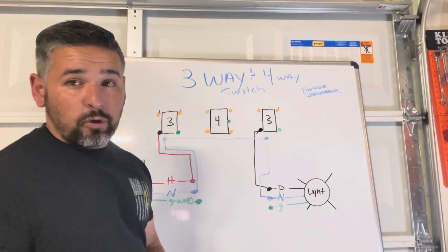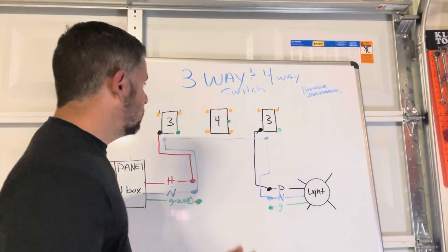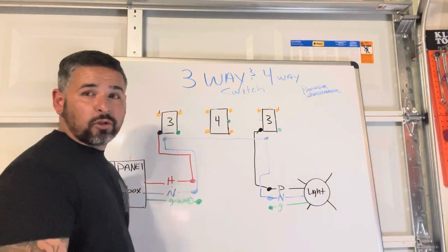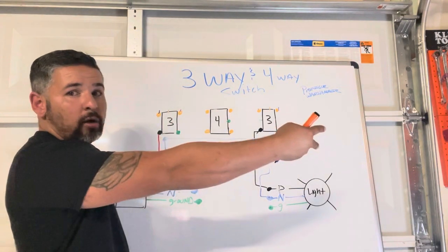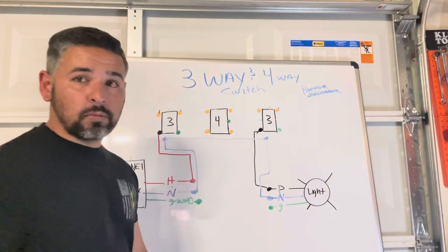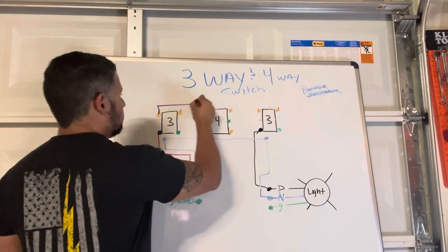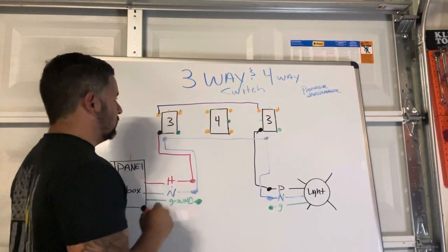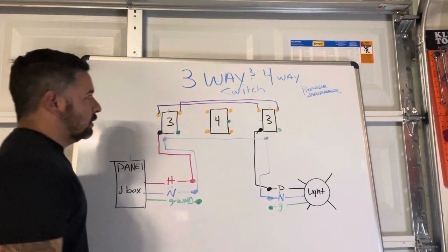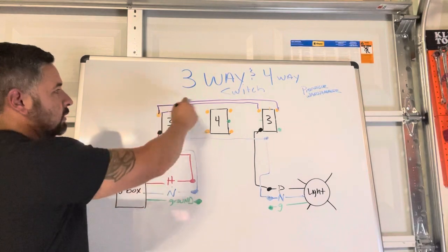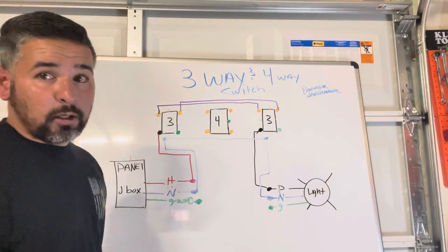So what do we do with these gold terminals on top? Those are gonna be your travelers, which is a terminology that electricians use to signify the two legs going across from three-way to three-way. So in this particular case we're gonna go there, so that's one of the pair of travelers, and then here's the second pair of travelers.